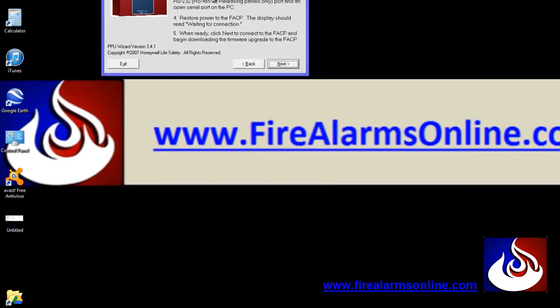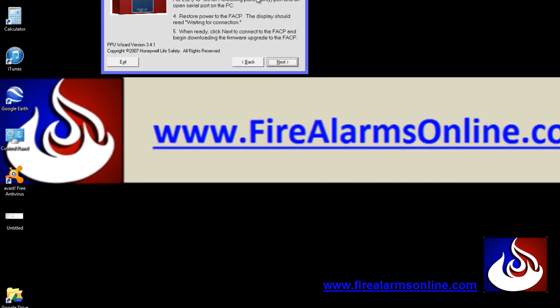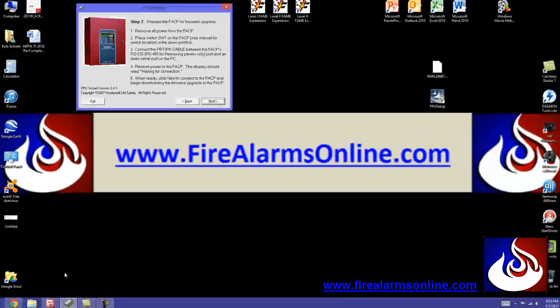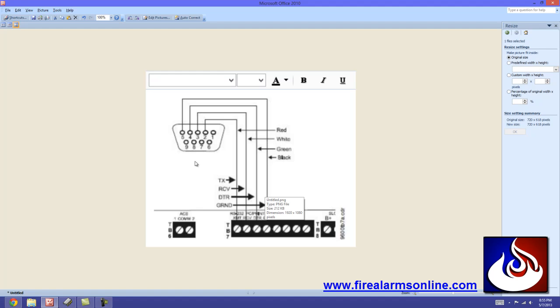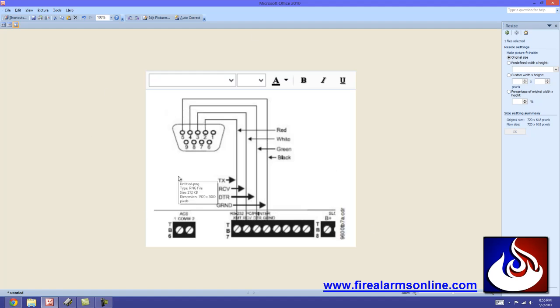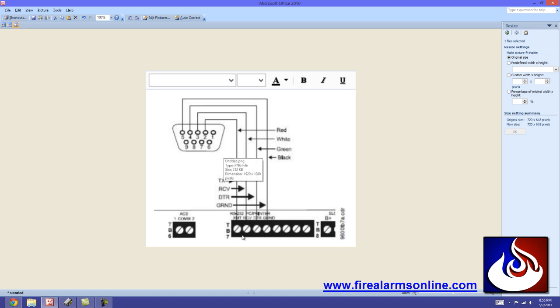And just in case you don't have this cable already, what I've done here, you can pause the video on this shot. But this is, like again, this is for the MS9600UDLS, so consult the book for other panels that you're going to be doing this upgrade to. I'm pretty sure it's all the same, but you've got pins 2, 3, 4, and 5, red, white, green, and black on the DB9 connecting to your TB7 here. So like I said, once again, this is for the 9600UDLS, confirm the wiring for the programming cable on the panel that you are doing the firmware update for.